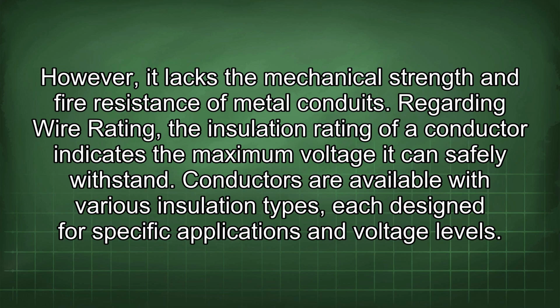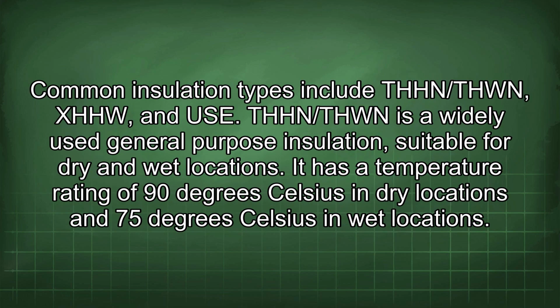Regarding wire rating, the insulation rating of a conductor indicates the maximum voltage it can safely withstand. Conductors are available with various insulation types, each designed for specific applications and voltage levels. Common insulation types include THHN/THWN, XHHW, and USE. THHN/THWN is a widely used general-purpose insulation suitable for dry and wet locations. It has a temperature rating of 90 degrees Celsius in dry locations and 75 degrees Celsius in wet locations.